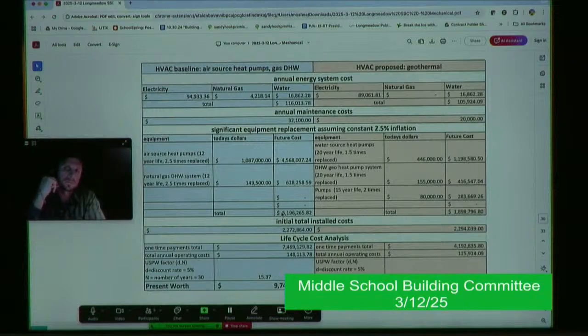That's one of the benefits of a geothermal system like this, because there are a lot of individual zones and pieces of equipment that are somewhat isolated. You do not need to preventatively replace heat pumps. If a heat pump fails in a particular classroom, it only fails in that classroom. Some of it can be repaired, like a compressor, but if it comes time for full replacement, that unit becomes isolated, the classroom shuts down for however long it takes to drop the old unit and install a new one, then the system is put back in service.